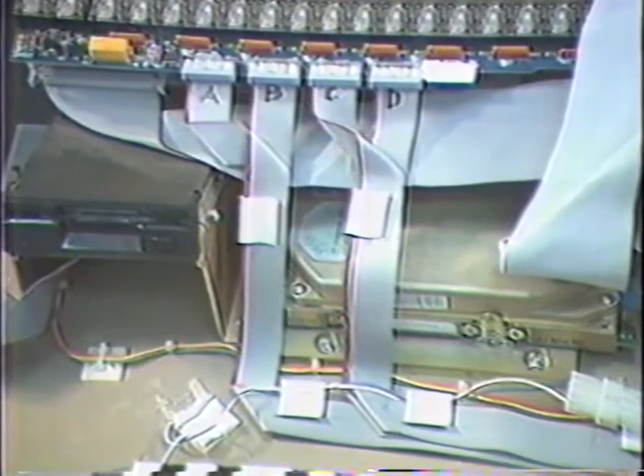Individual channels not working. If an individual channel is not working, check the output board to analog jack cables. D cable carries channels 1 through 4. C cable carries channels 5 through 8. B cable carries channels 9 through 12. And A cable carries channels 13 through 16. A bad channel may be caused by poor contact or contamination of these cables.